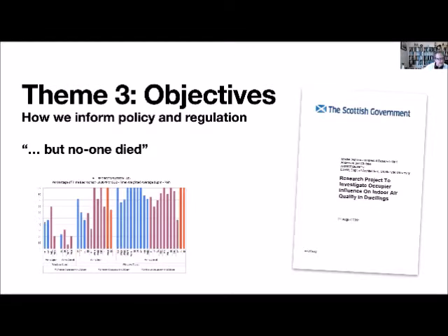There are various things. I mean, how informed policy and regulation is interesting and important. This is a bit of work we did for Scottish building regs, in which we demonstrated that the use of trickle vents wasn't really doing enough in airtight buildings, and therefore it was all terrible. They need to change the regulations.